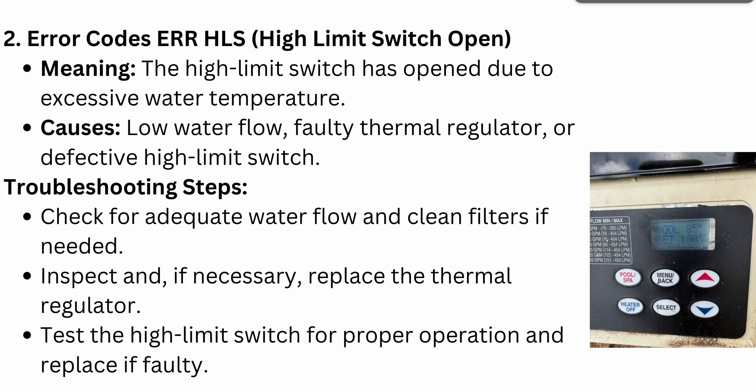The next error code is ERR HLS — high limit switch open. As you can see it is showing here. It means the high limit switch has opened due to excessive water temperature — when the water temperature rises excessively, this code shows. The causes include low water flow, a faulty thermal regulator, or a defective high limit switch.